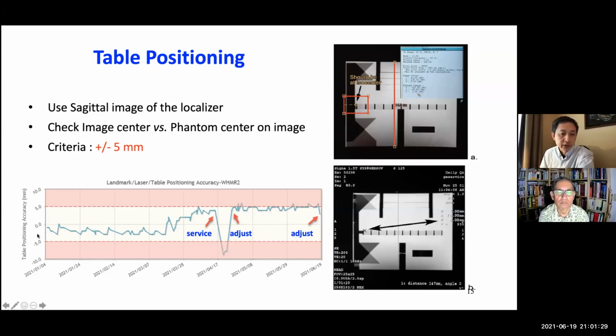So here I'm showing you a daily table positioning result of one of our scanners. And you can see starting from sometime about March this year, the table position accuracy started to change. However, it's still within the ACR limit, so we didn't call the service. And at a certain time, the service came in. Actually, this is a routine service. We didn't call them. This is just a quarterly PM. And after the PM, the table accuracy became very bad.